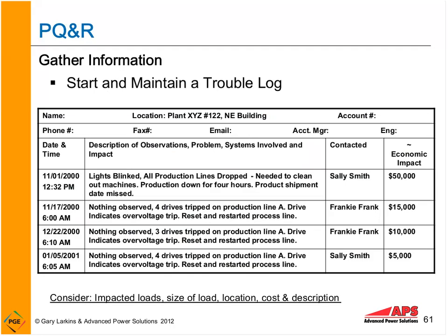Start and maintain a trouble log. How do we know when it's happening and what is happening in the facility unless we start to document it? So are we seeing these daily? For an example, when I started that project at the airport, when is it occurring? They say, well, every morning between 4 and 6. Immediately, I already had an idea of what was happening on the system based on when they told me it was happening. So how about you?